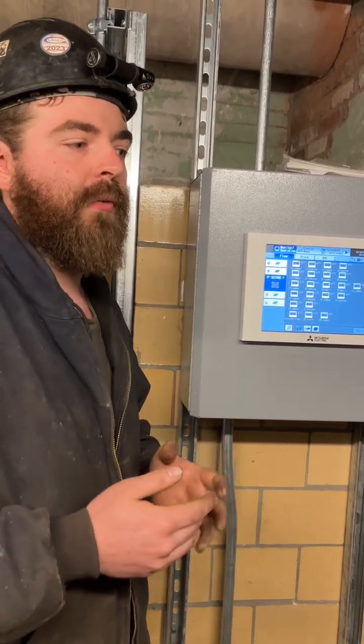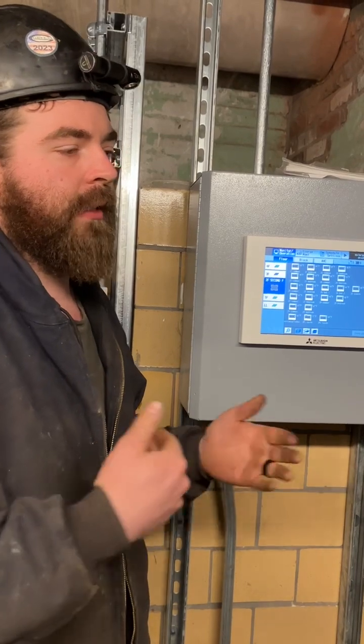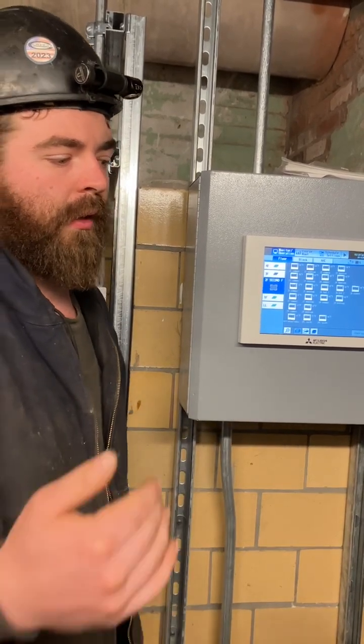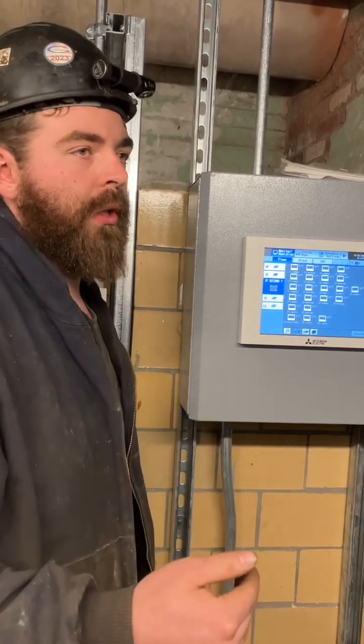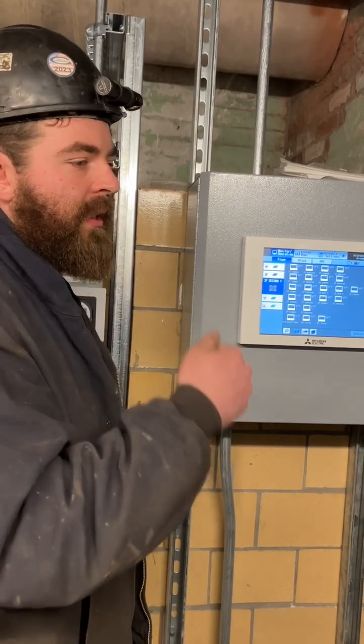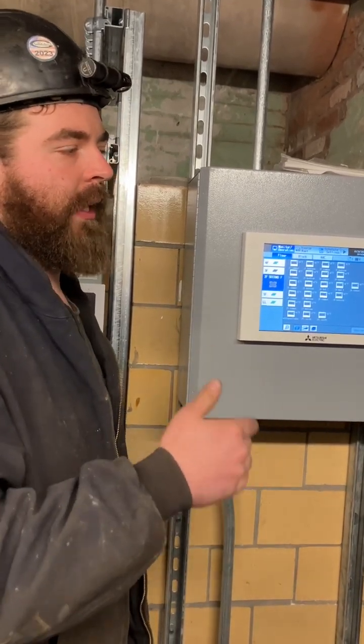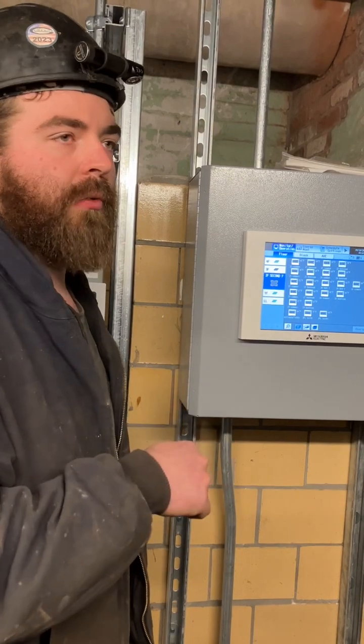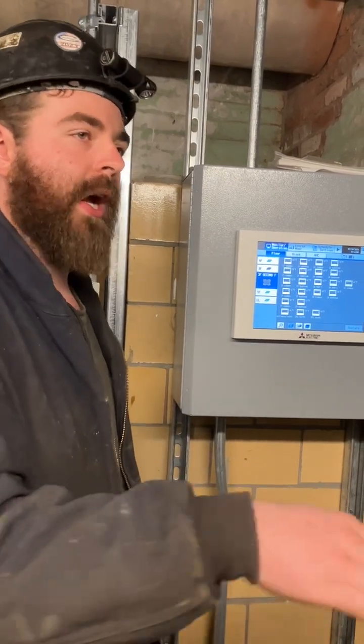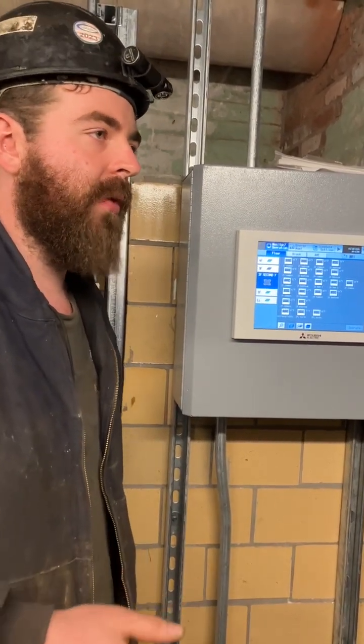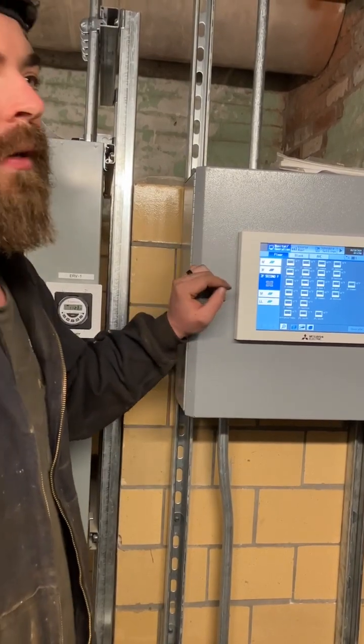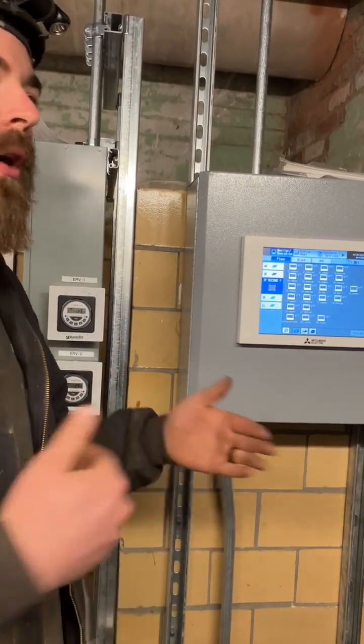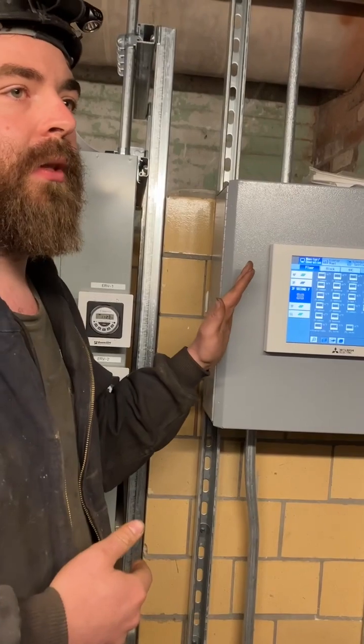But I have a feeling that if we break that on the Pelican system, so we have the bedroom be a cooling-only thermostat, and then temporarily disable the 2nd stage of heating for the main room thermostat, the baseboard runs through the entire apartment. I think they run a little bit better, but these do have the capability of doing that. The easiest way to break that apart is through the Pelican. I wouldn't try to do it with this.